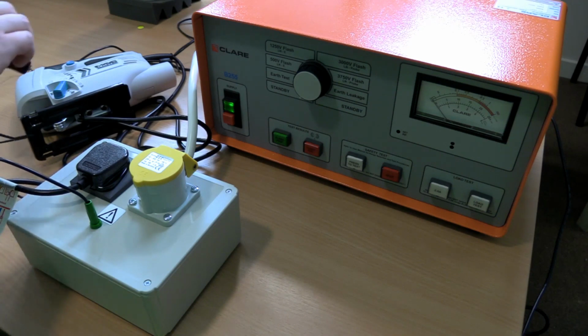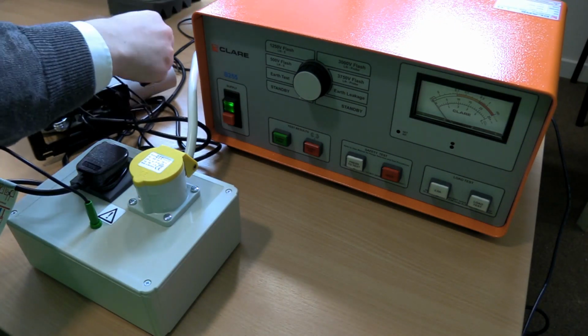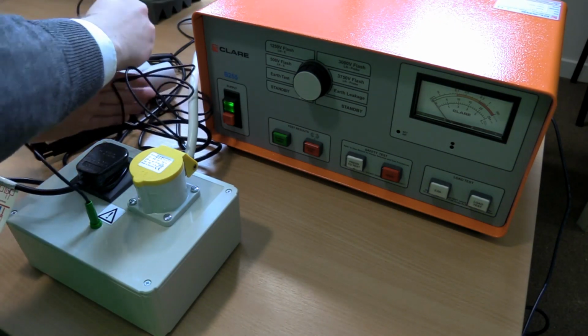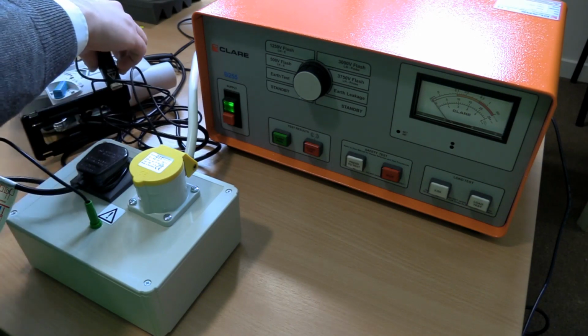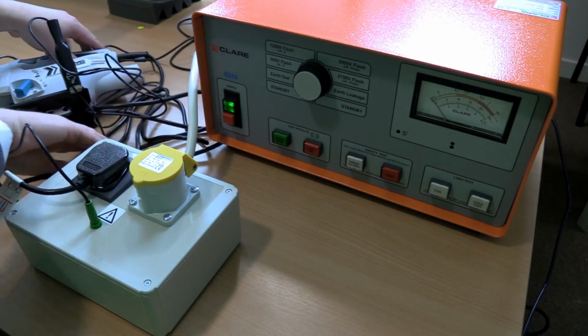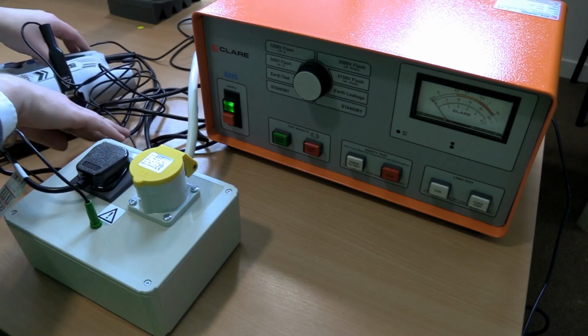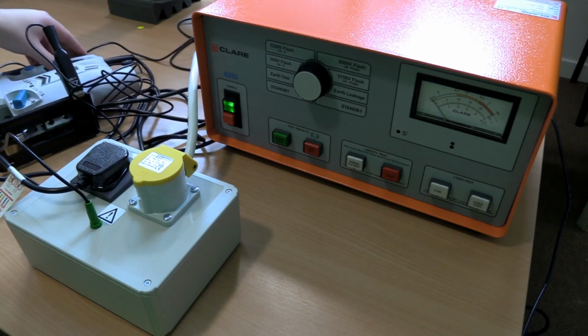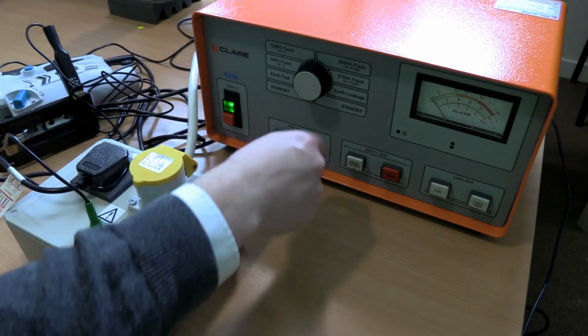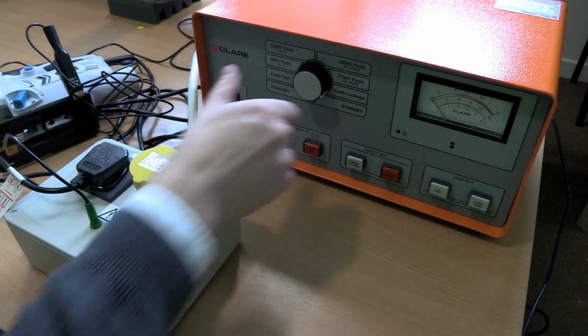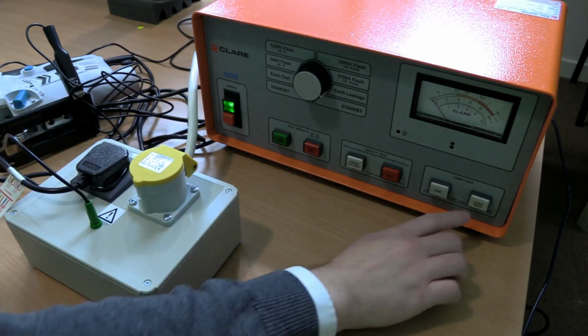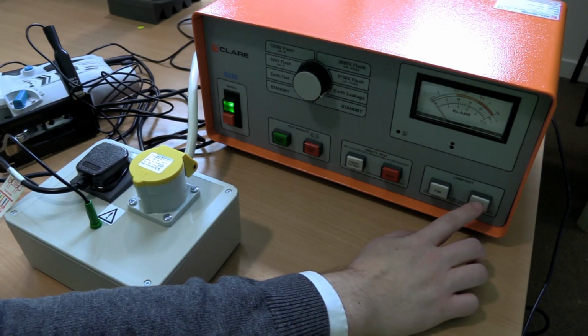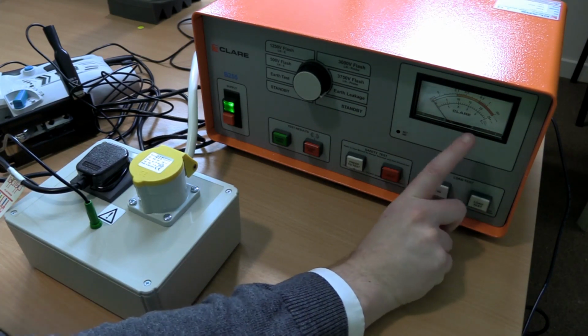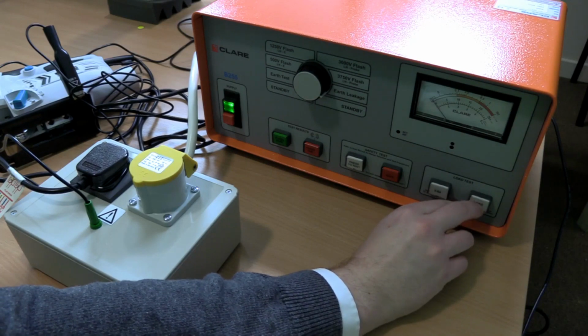I'm going to then clip my clip onto part of the exposed metal that's not going to move when I start this test, because remember, the touch leakage test is going to power up the equipment. So the moving parts of the equipment will start to move as soon as I press go. I'm going to go onto earth leakage, which is this one here, and then I'm going to hit the load button, and we're going to power up the equipment and get a touch leakage measurement on this bottom scale here.